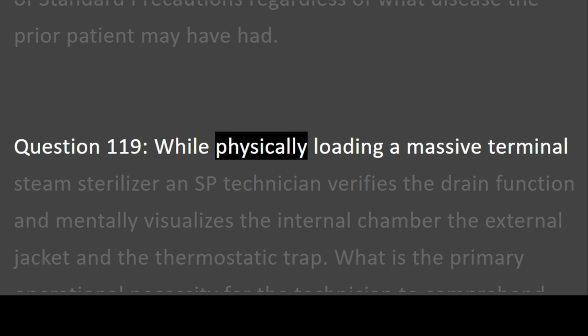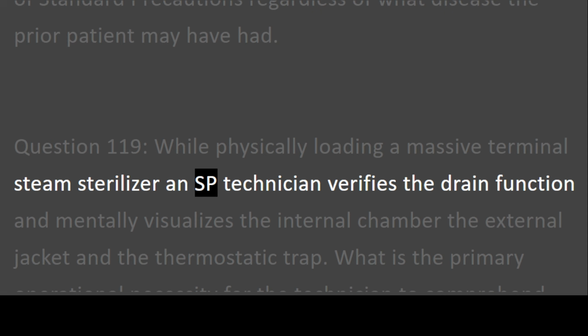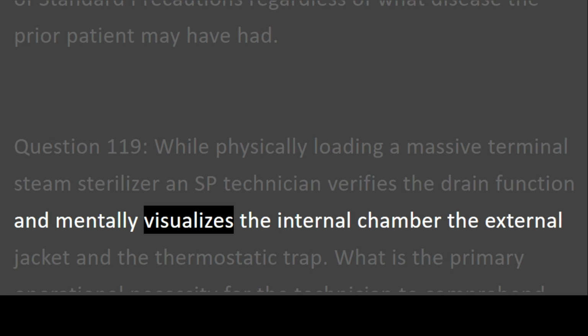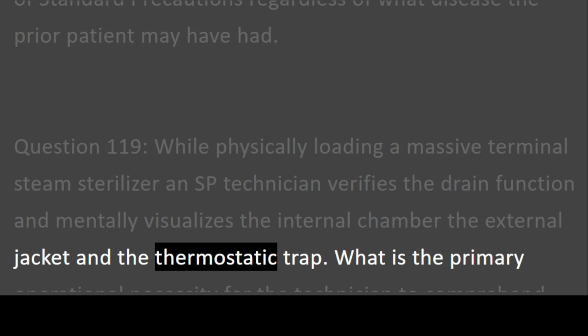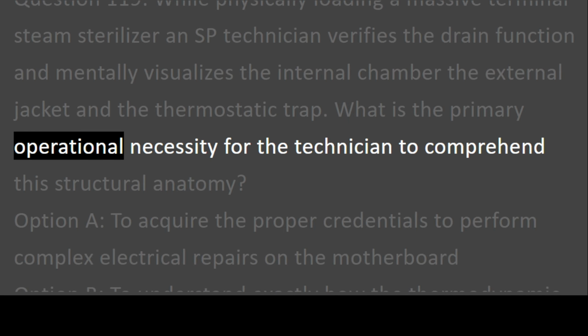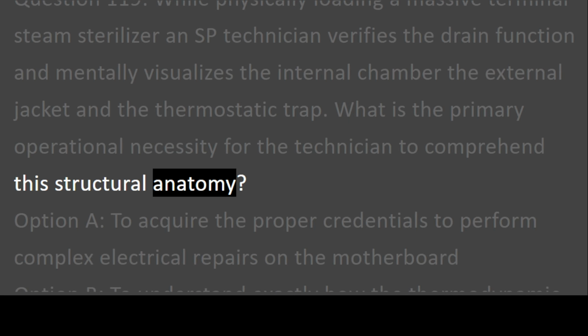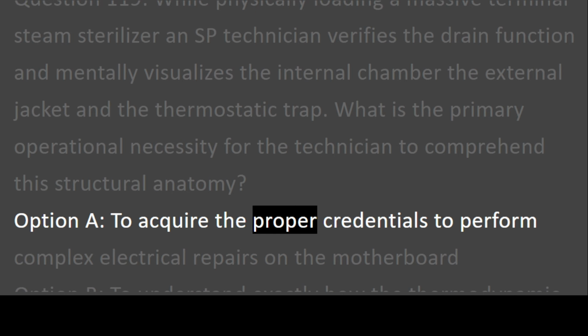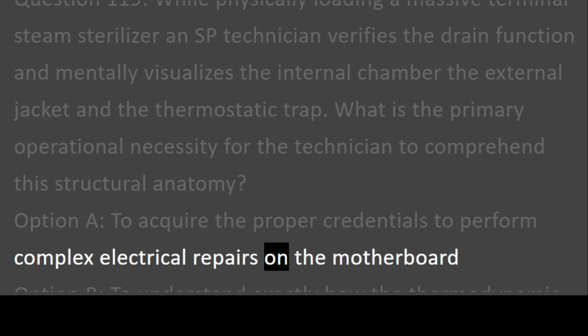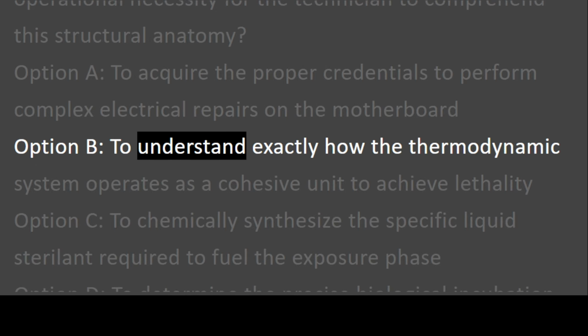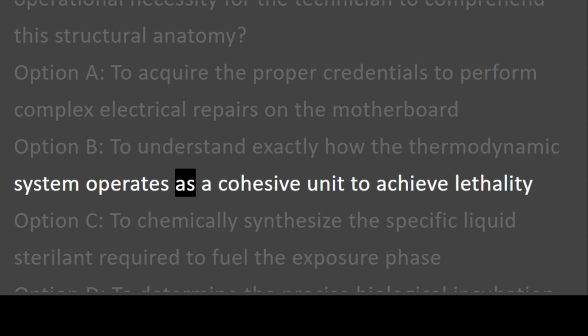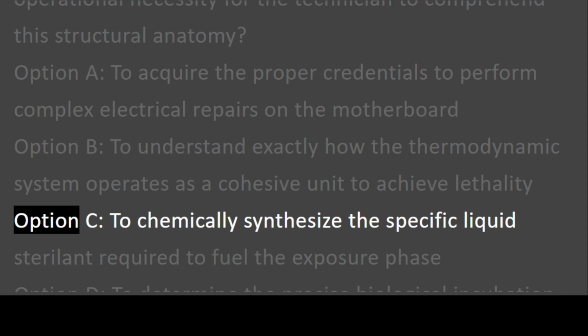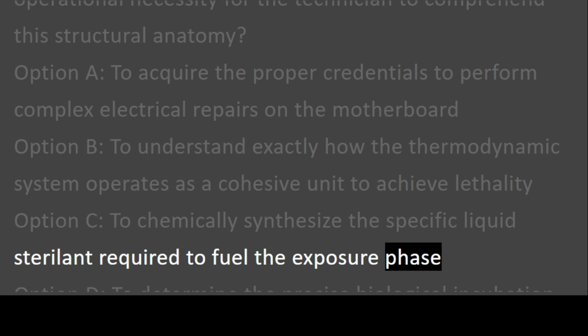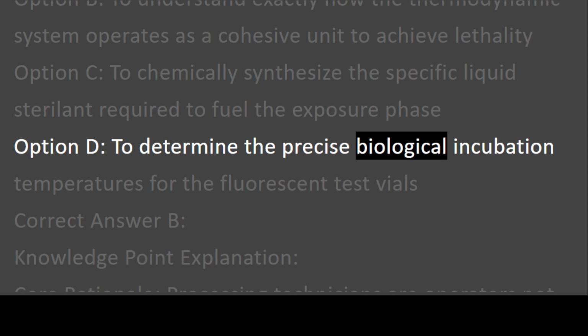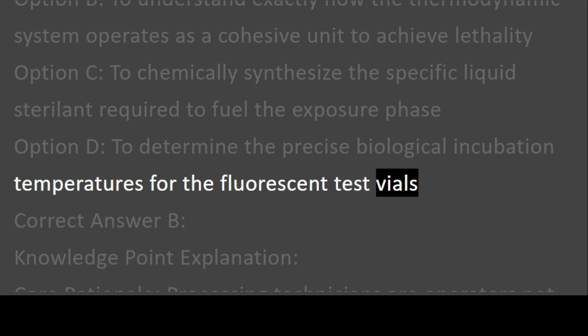Question 119. While physically loading a massive terminal steam sterilizer, an SP technician verifies the drain function and mentally visualizes the internal chamber, the external jacket, and the thermostatic trap. What is the primary operational necessity for the technician to comprehend this structural anatomy? Option A. To acquire the proper credentials to perform complex electrical repairs on the motherboard. Option B. To understand exactly how the thermodynamic system operates as a cohesive unit to achieve lethality. Option C. To chemically synthesize the specific liquid sterilant required to fuel the exposure phase. Option D. To determine the precise biological incubation temperatures for the fluorescent test vials.